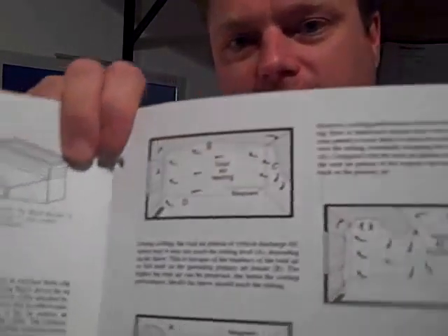Very pertinent information. Mentioned Manual T, talking about moving air over surfaces. It's describing moving air over a ceiling, and talks about extending the throw by doing this. And you may ask, well, why would you want to do that? You had mentioned that you'd set your floor registers out 12 inches away from the wall. Well, I understand that you're using a balometer, and your balometer is 2 foot square, and you want to center it up under the cone so you get an accurate reading.